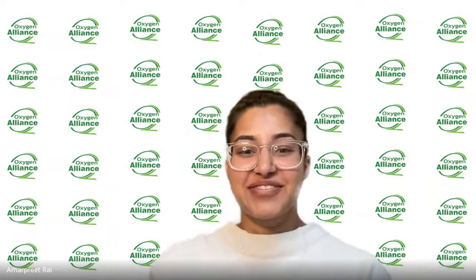Fraser, please go ahead. Yeah, I don't want to put Tom and Danny on the spot, but one of the things I was just thinking is the guys were delivering the presentations. We spoke a lot about service manuals, install guides, and test sheets. But correct me if I'm wrong, Amapreet, potentially some of these units that are out there in the field won't have that level of documentation with them, or it may be that they've been lost. So I think some of the fault finding stuff that you ran through, Danny, may be able to help with that. But if we were to assume that level of documentation wasn't present with the generator, is there a good place that people could start from? For any units? Yeah, for fault finding, if the service manual or the install guide wasn't there, is there something that they could start with, assuming it wasn't a Peak unit?